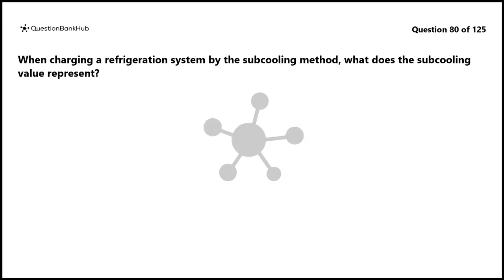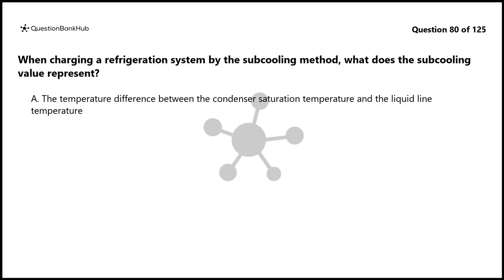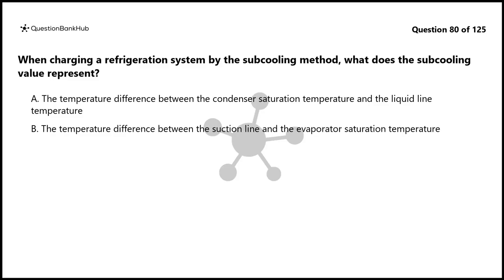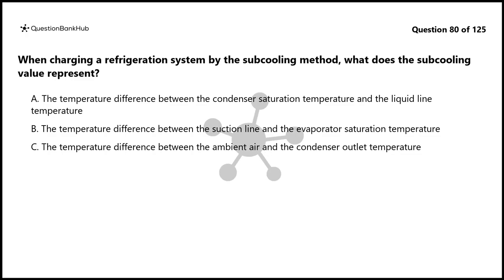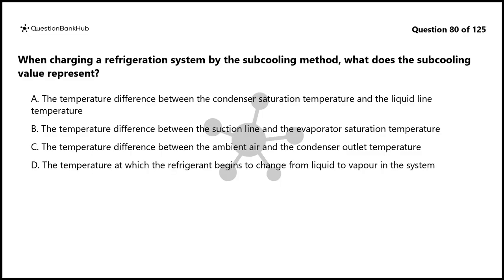Question 80. When charging a refrigeration system by the subcooling method, what does the subcooling value represent? A. The temperature difference between the condenser saturation temperature and the liquid line temperature. B. The temperature difference between the suction line and the evaporator saturation temperature. C. The temperature difference between the ambient air and the condenser outlet temperature. D. The temperature at which the refrigerant begins to change from liquid to vapor in the system.